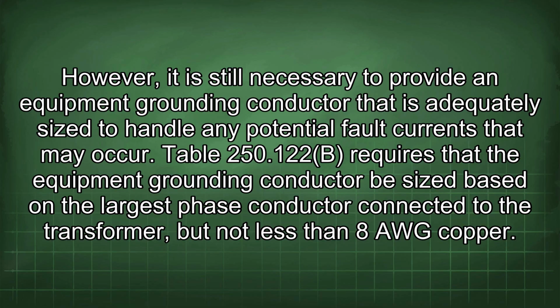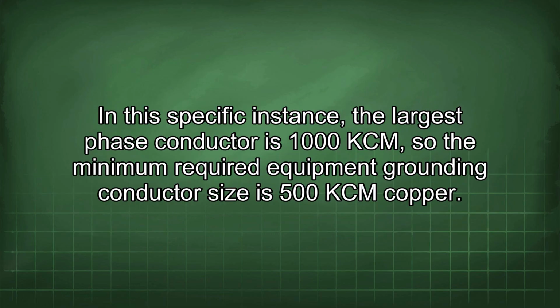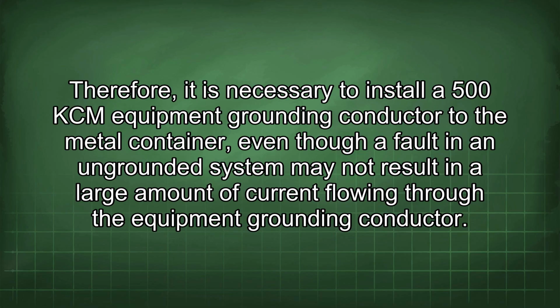currents that may occur. Table 250.122(B) requires that the equipment grounding conductor be sized based on the largest phase conductor connected to the transformer, but not less than 8 AWG copper. In this specific instance, the largest phase conductor is 1000 kcmil, so the minimum required equipment grounding conductor size is 500 kcmil copper.